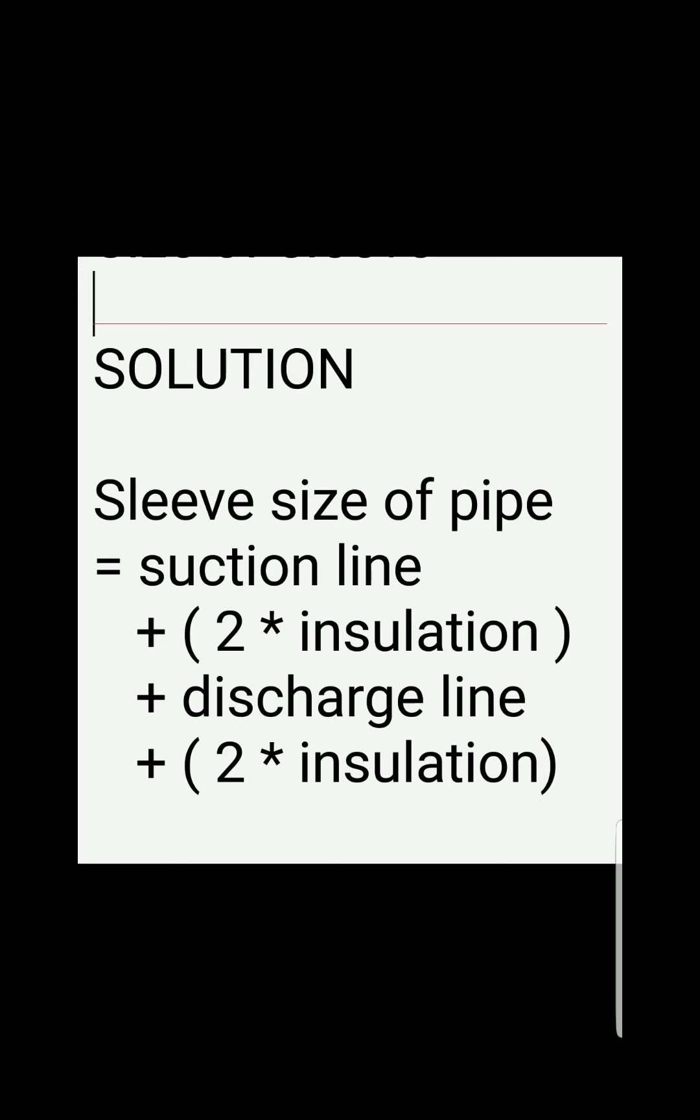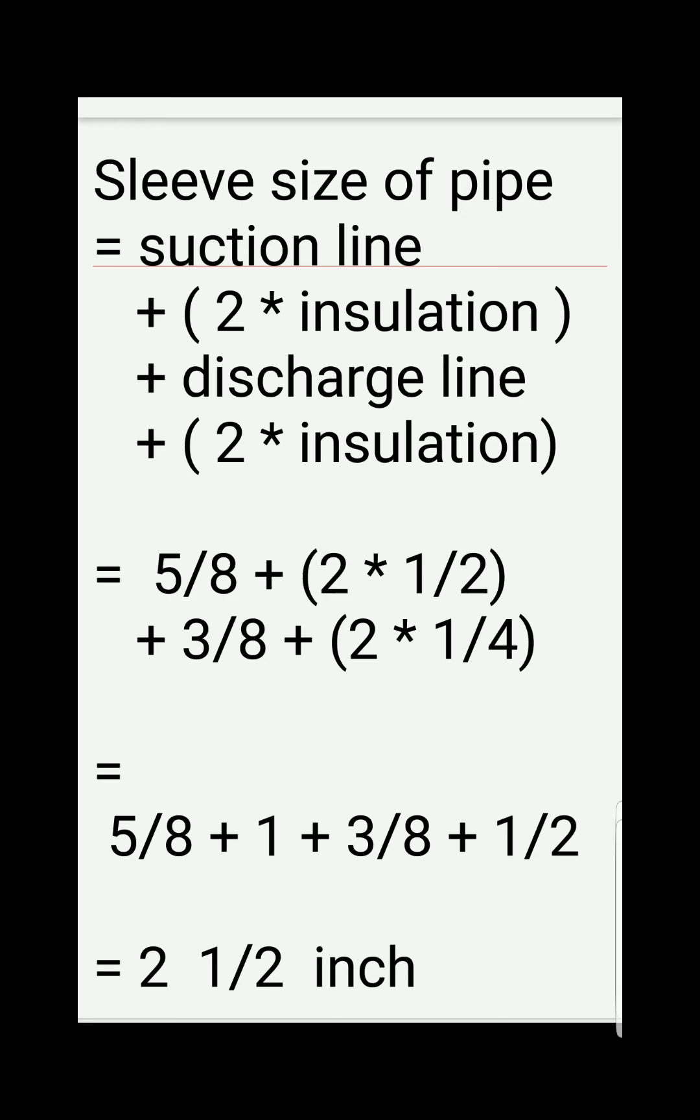The solution: the sleeve size of pipe is equal to the suction line plus twice the insulation of the suction line plus the discharge line plus twice the insulation of the discharge line. So now we substitute the given.